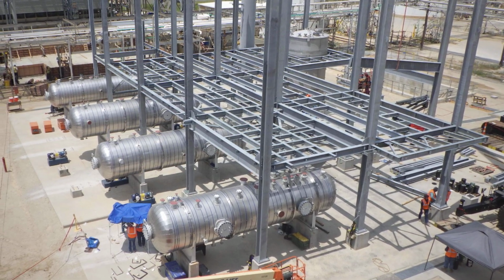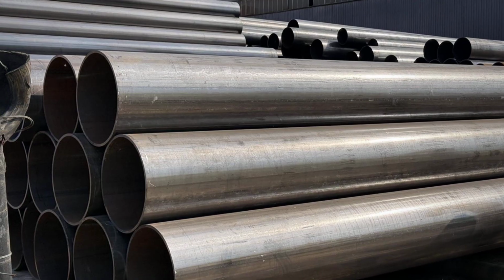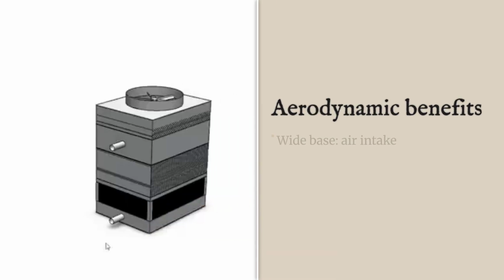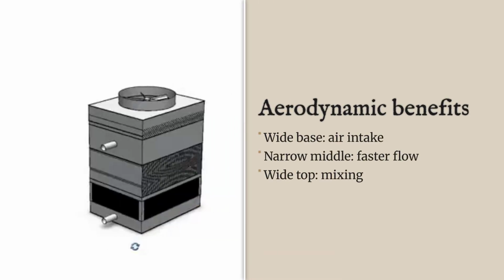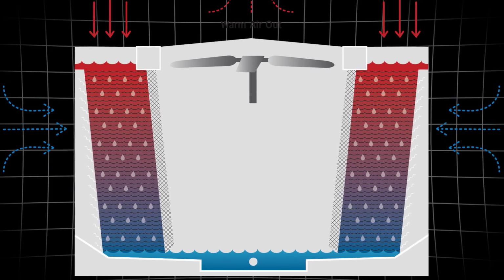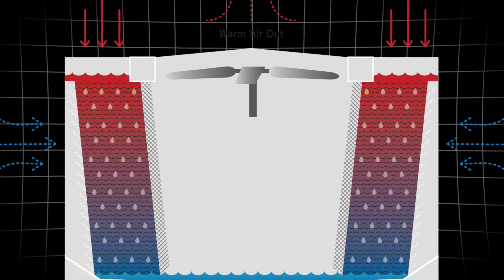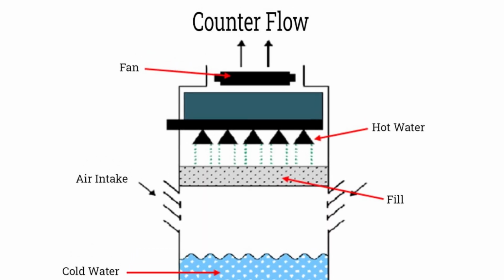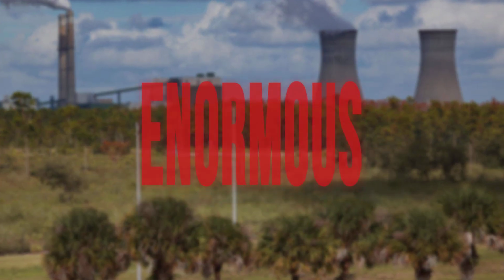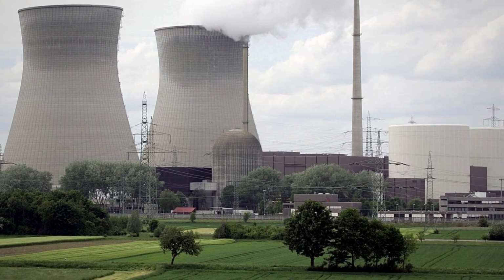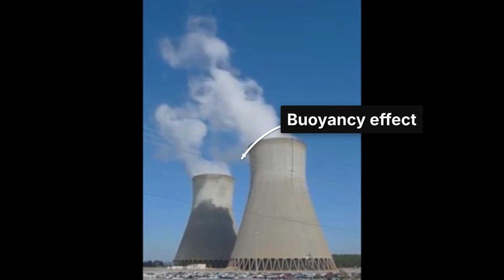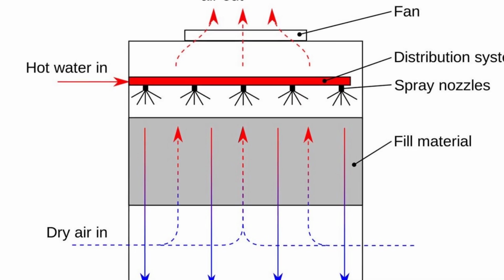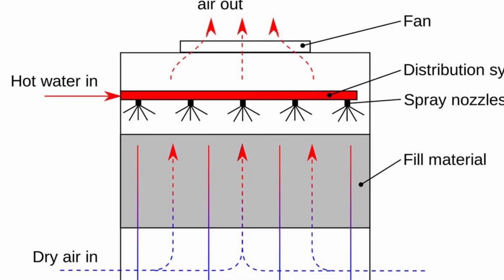However, straight lines alone aren't the sole driver of this design. A cylinder also uses straight lines. While the hyperboloid offers aerodynamic advantages, its wide base allows ample air intake, the constricted middle accelerates upward flow, and the wider top promotes mixing with ambient air. These are actually secondary benefits. The primary reason for this distinctive shape is structural. These towers are enormous. To achieve sufficient natural convection, a tall stack is essential. The taller the tower, the more warm, humid air it contains, generating greater buoyancy and increased airflow.